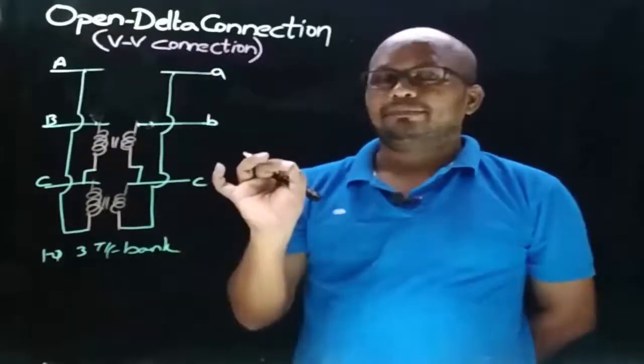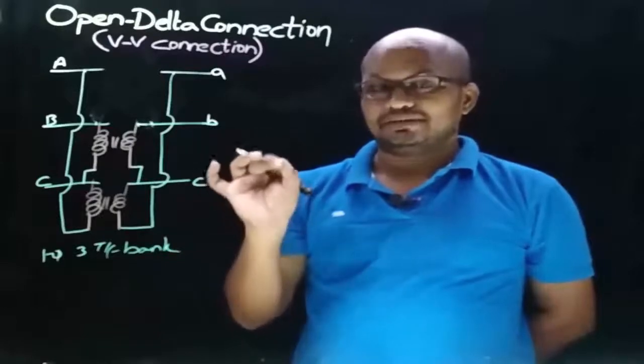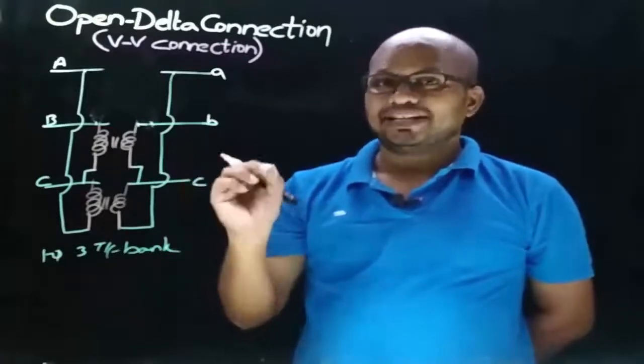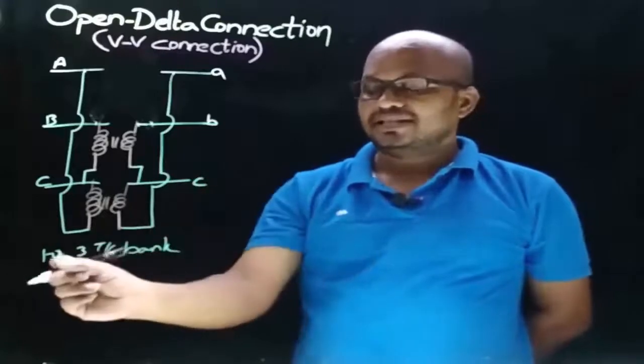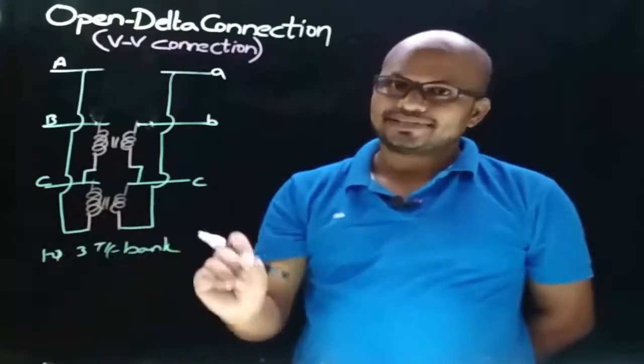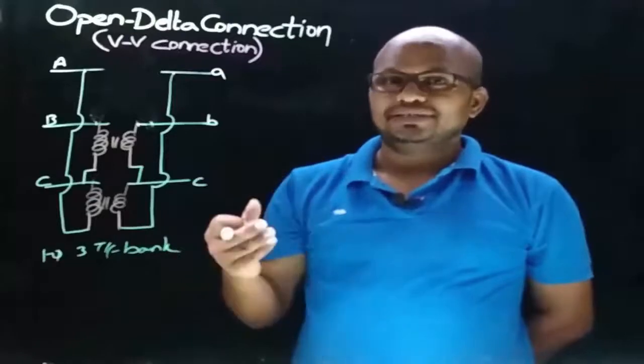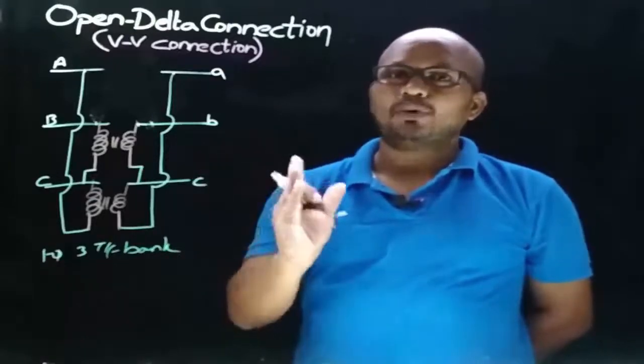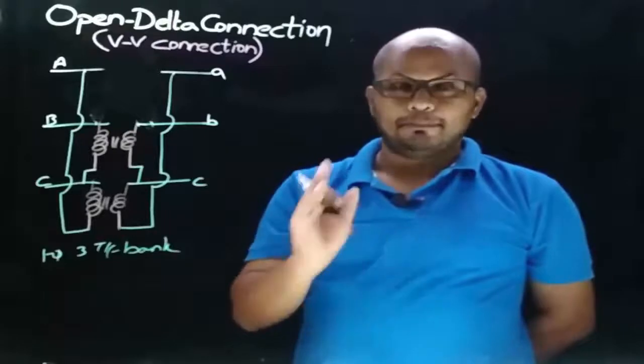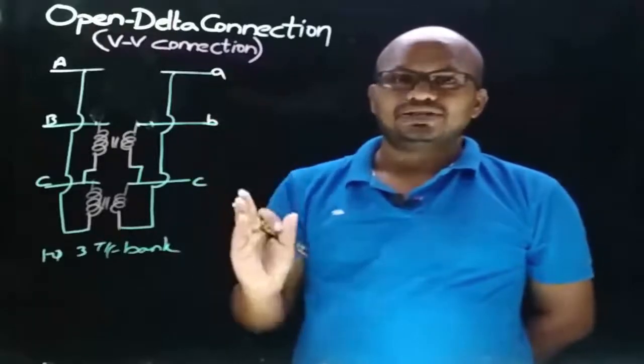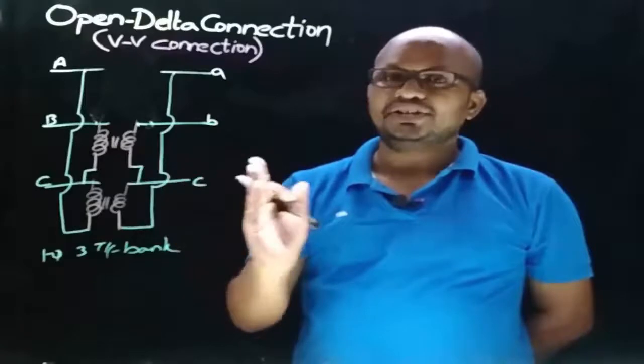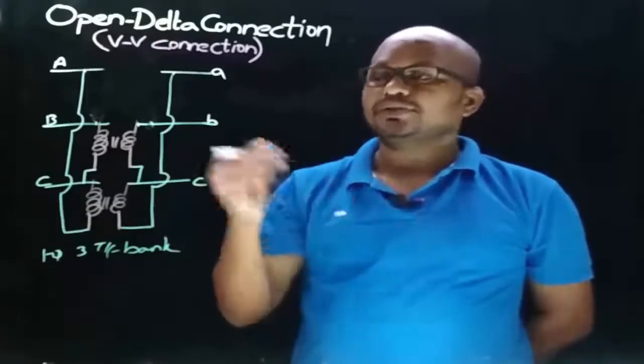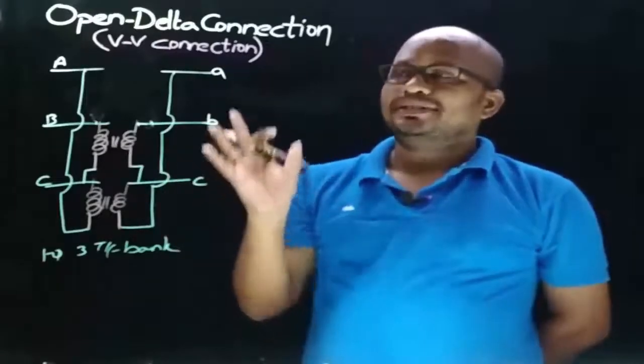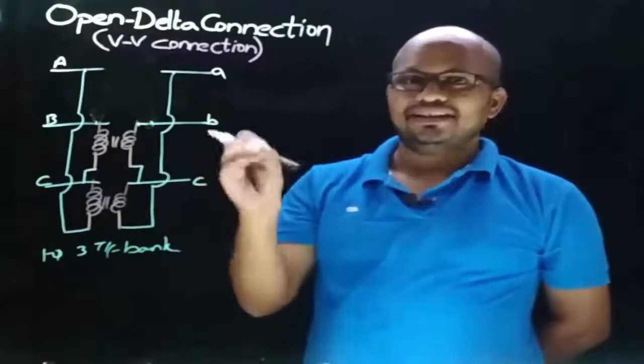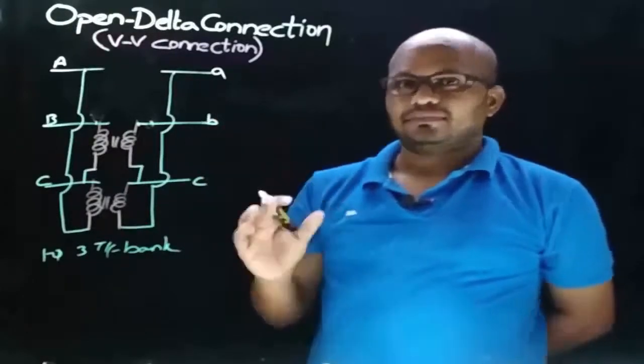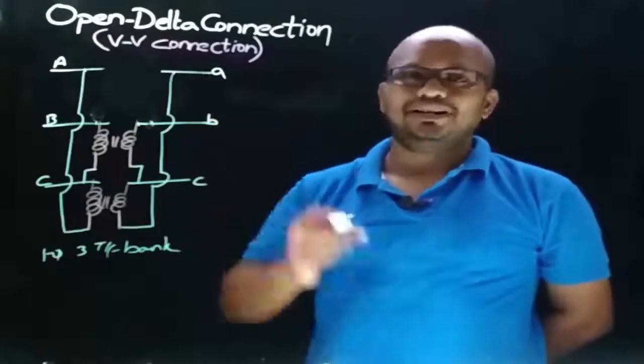delta connection. And I request you to keep this point in mind: when one of the transformers in a delta-delta connected single phase 3 transformer bank gets failed, then obviously we think that there will be power interruption to the load. But with open delta connection, we can maintain the continuity of supply to the load, but with reduced capacity. To make the discussion simple, let's redraw the delta-delta connection in a simple manner and observe the open delta connection.